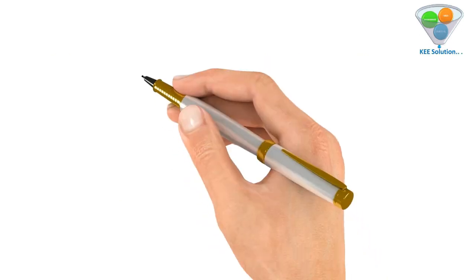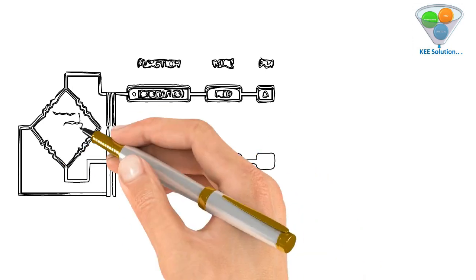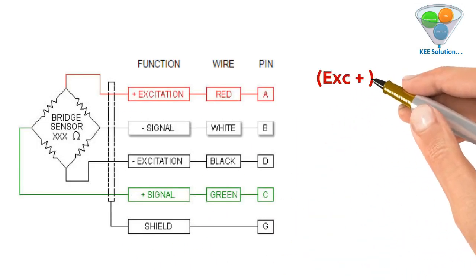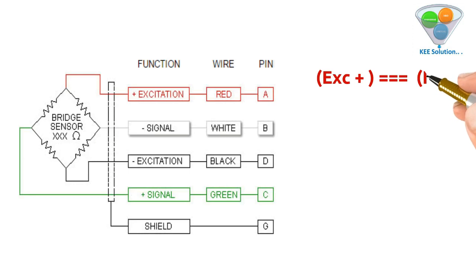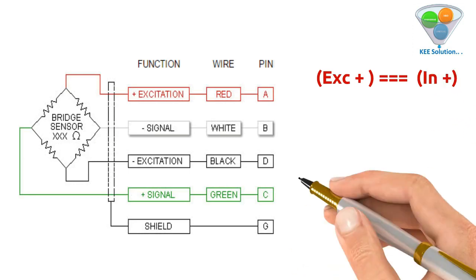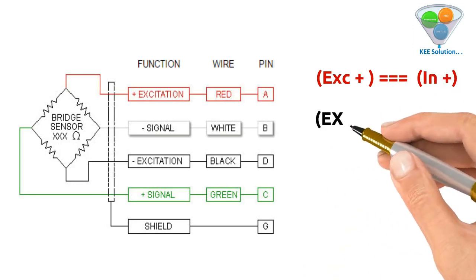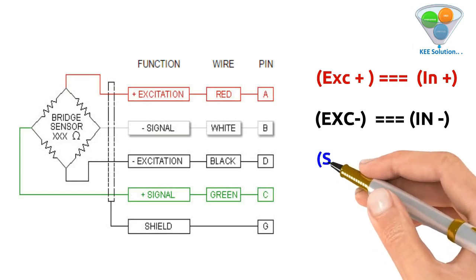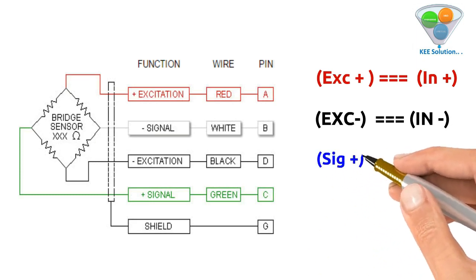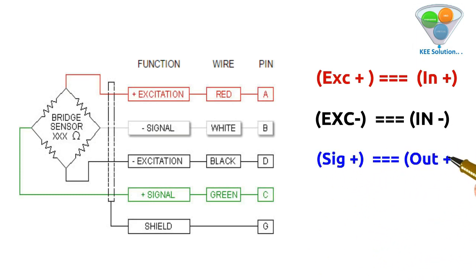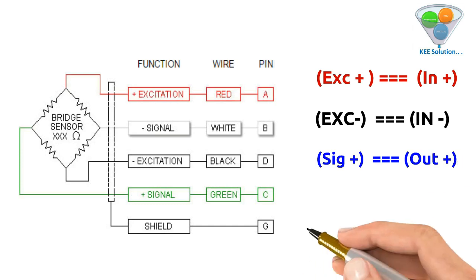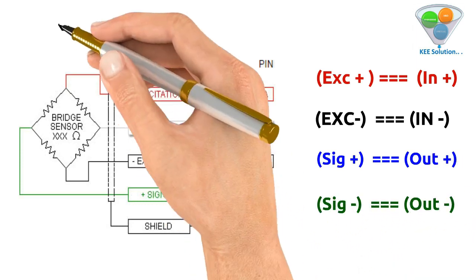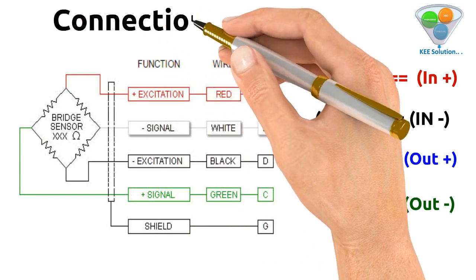We face many problems connecting a load cell to a controller or display or indicator because different brands have different nomenclature. These are some common nomenclature: excitation, signal, and input/output details. In the bridge circuit there is excitation positive, excitation negative, signal positive, and signal negative.